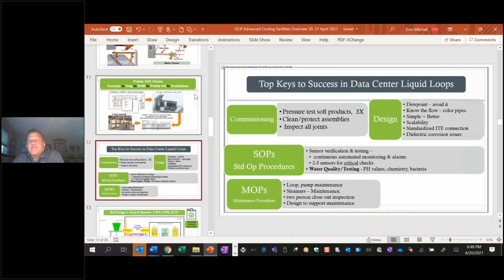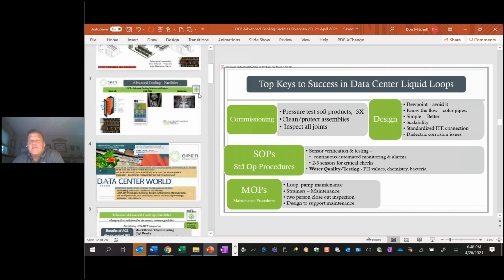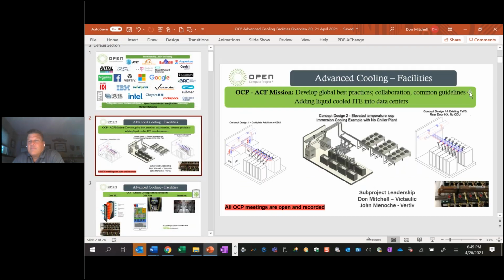But one thing we're finding with a lot of these solutions, immersion tanks, you can actually cool immersion tanks with 45 degrees centigrade liquid. Cold plate, you can cool those with 35 to 45 degrees. There are very few places where 45 degrees centigrade will give you condensation. Even in Singapore, 45 won't get too much, maybe someone can comment on that, but you're above the dew point in most regions, pretty much every region.